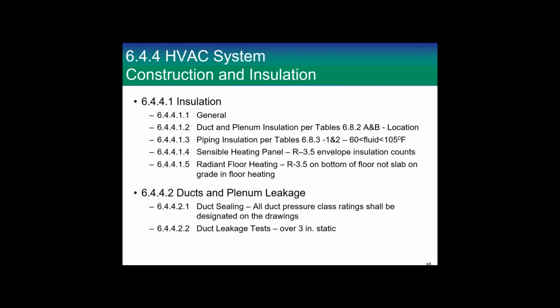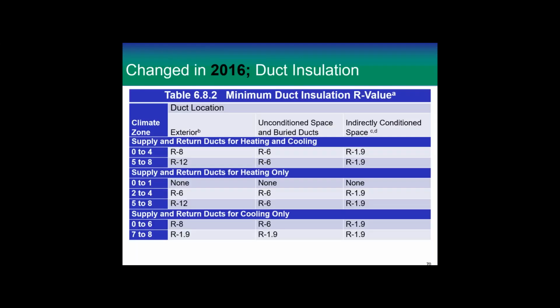We also have that you have to insulate the back of a sensible heating panel so that you don't heat the ceiling, the room above you. And radiant floor heating, this is not the slab, but if you have a radiant floor like on the second floor or the third floor, you have to insulate again to keep it from heating the floor you don't want to be heating, going down if you're on the second floor. Ducts and plenum leakage: all duct pressure class ratings shall be designated on the drawings, and duct leakage tests for over 3 inches of static. The seal class has to be A to meet 90.1. SMACNA has seal classes. They allow A, B, and C, but to meet 90.1, you have to only use A.